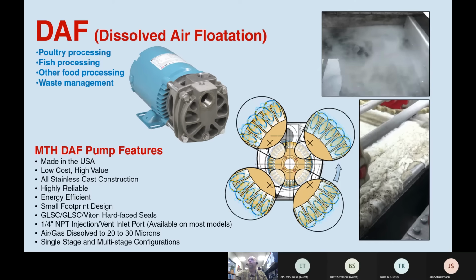Here's the DAF process I had referred to earlier. You can see this is what I was referring to when it mixes up the air. You can see in this picture, this pump has a hole in it. You wouldn't hook up a compressor to it. You would simply put a valve on it, and turn on the pump, and as it's circulating the water into the tank, you would open up that valve and get the amount of air pressure that you wanted. The pump would naturally suck the air in itself. You wouldn't have to use any kind of compressor. And with that, all you would have to do is visually look and dial in when you see the right amount of, I guess I just call it, smoke. When you see the right amount of smoke in the water, then you have the DAF effect going, and it'll grab any particles that are in that water and pull them to the top where they can just be skimmed off.